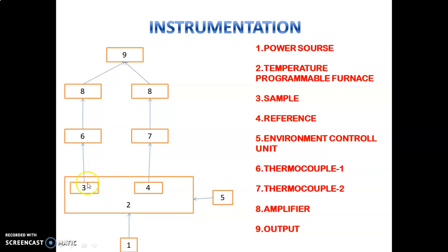We need to measure the temperature of both the sample and the reference simultaneously. That is the reason we require two thermocouples. Thermocouple one measures the temperature of the sample, and thermocouple two measures the temperature of the reference material. The difference in temperature between the sample and the reference is also measured. This data is provided to the amplifier, which amplifies the data and sends it to the output. The output produces a spectrum known as a differential thermogram.